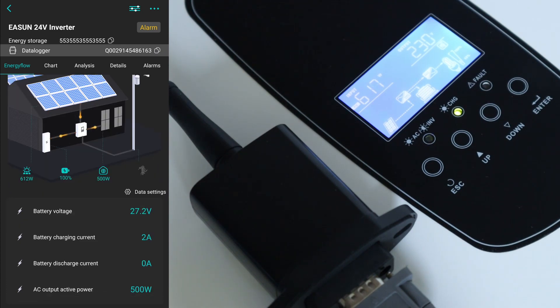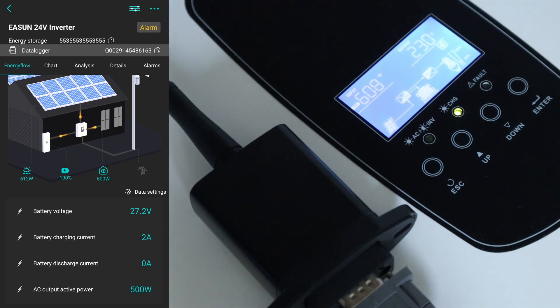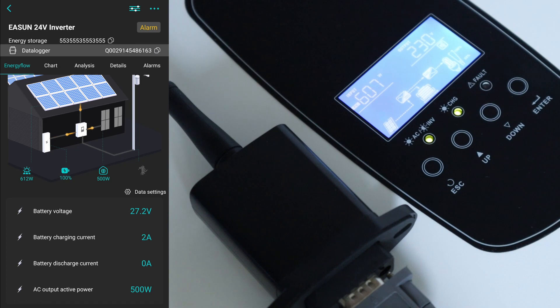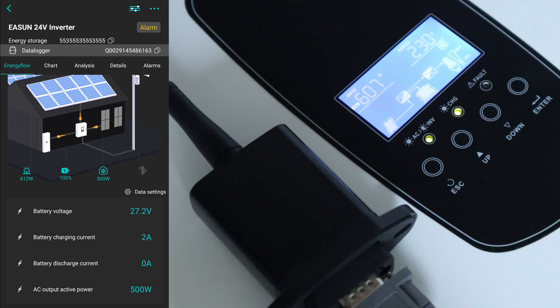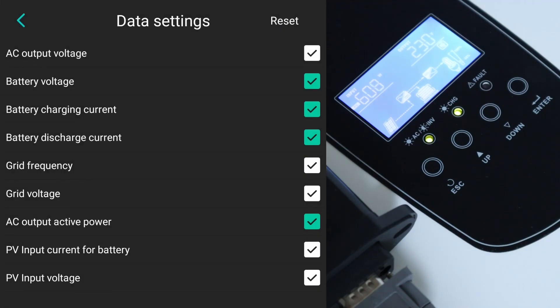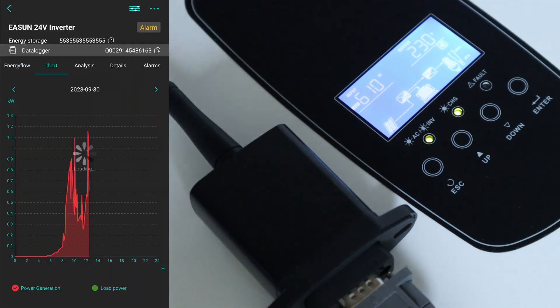And again, this is a point in time, so it updates regularly, but I'll show you that on some of the other tabs inside. So as you can see at the moment the battery is full, so it's sitting around the float voltage of 27.2 - it's what I've got it set to on this particular setup. And underneath you can see various stats I'm interested in, so the battery charging current and battery discharging current, and also the active power. So that's how much is coming out really out of your AC output on this. And if you click on data settings there you can actually change what you view in there as well.